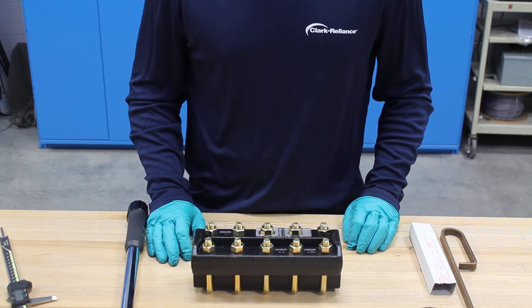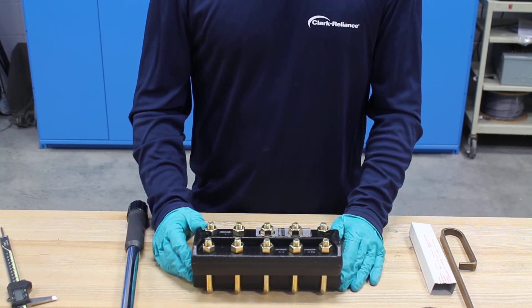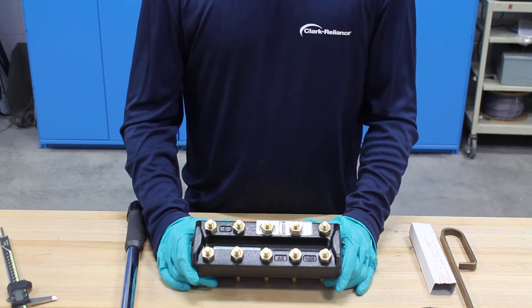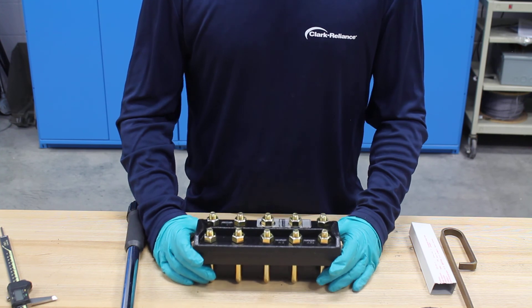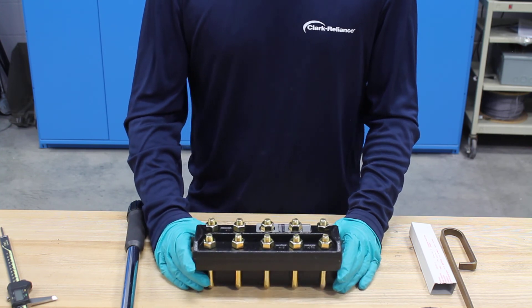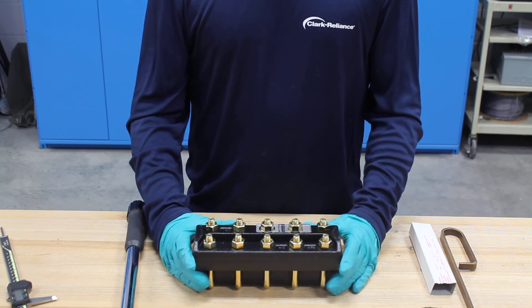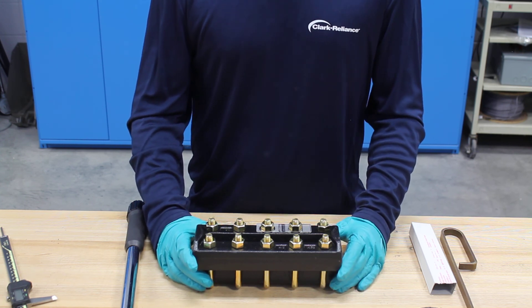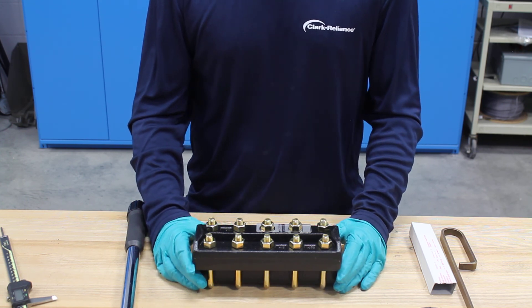Now the gauge is rebuilt. Just before you install it, all reassembled gauges should be hydro tested for a minimum of five minutes before returning to service. It's recommended that the hydro test pressure is one and a half times the gauge rating as seen on the tag. That pretty much concludes this instructional maintenance video. For more information visit our website at www.jerguson.com.